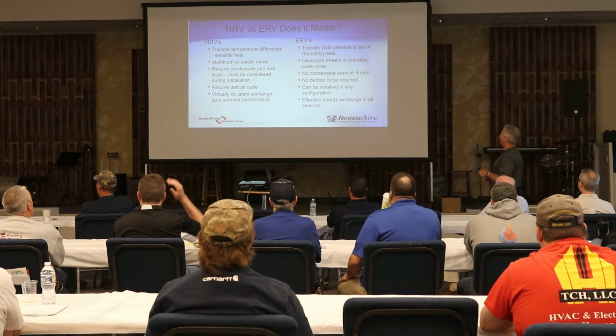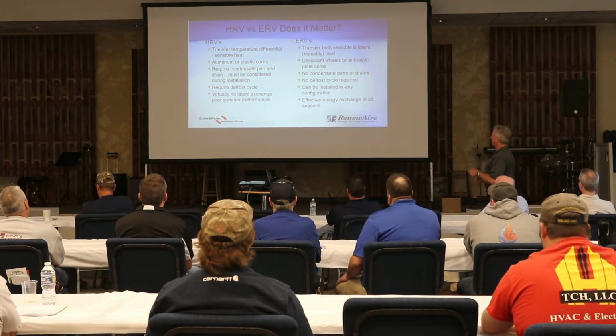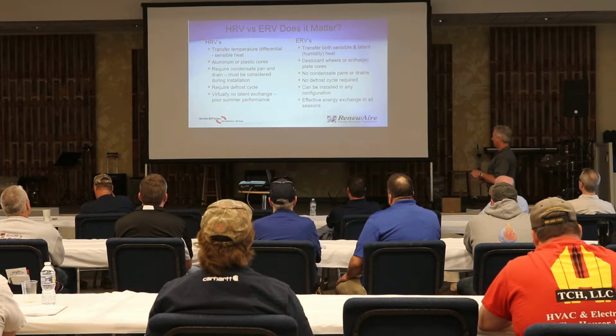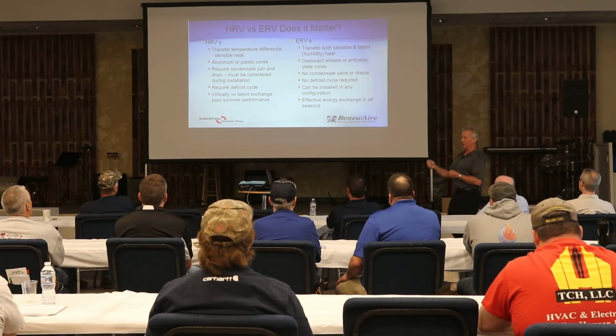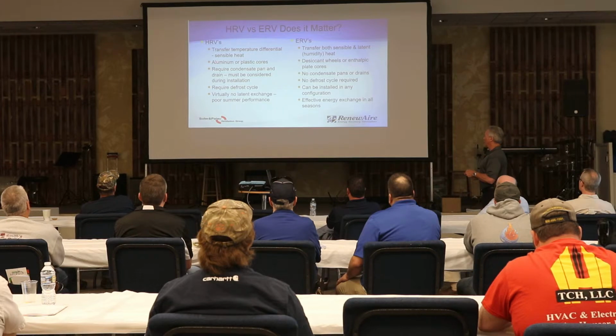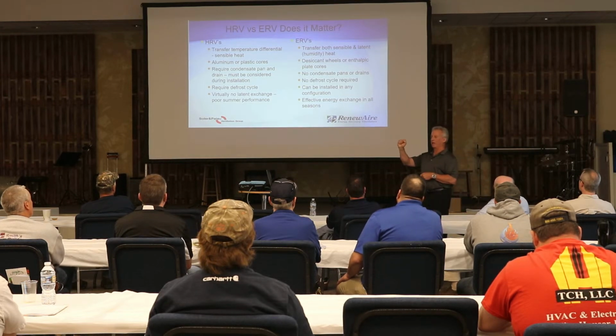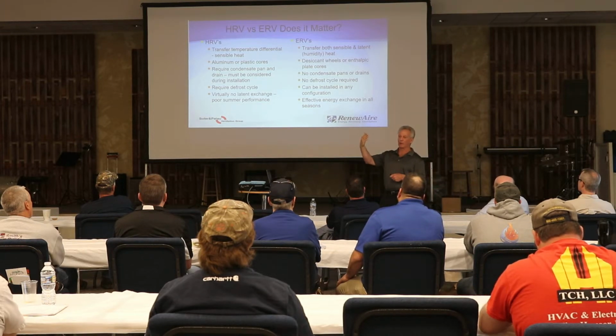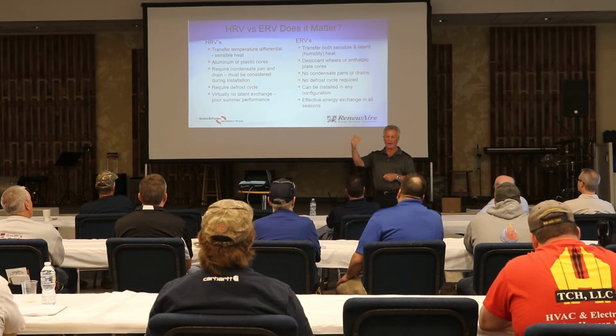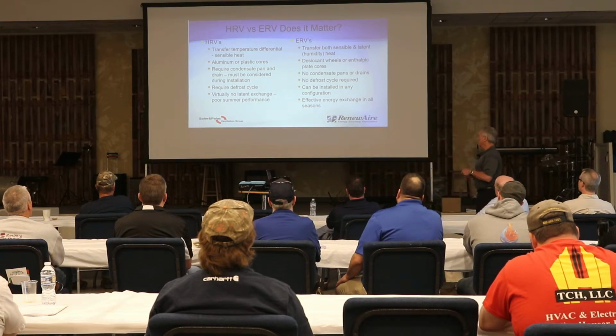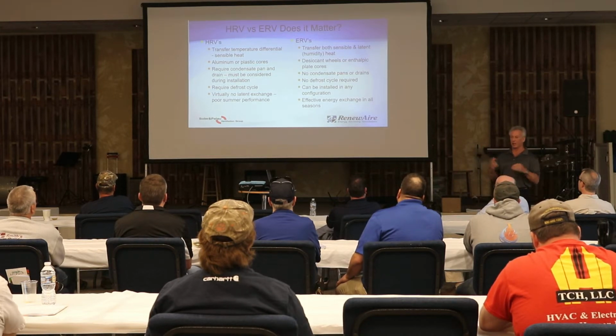Okay, just to cover, we do feel that there's a big difference between heat recovery ventilators and energy recovery ventilators. So let's look at what a heat recovery ventilator does first. It transfers temperature differential through the core, and that is sensible heat only. It makes use of aluminum or plastic cores. Because it's transferring sensible heat only, but there's always a latent component in the air, you're likely to get condensation on that aluminum or plastic core. The aluminum can freeze, but at the very least, you're going to require a condensate pan and a drain, and that must be considered during the installation process.